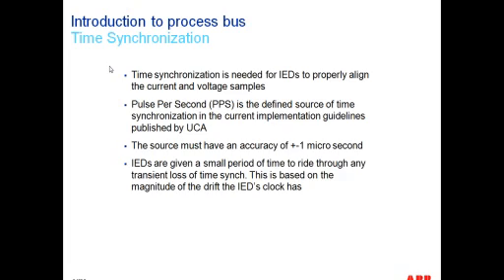Once that allowable time expires, and that time again is based on the drift of the clock, the samples published by that merging unit will have a false in the flag of that Ethernet frame associated with time synchronization. And based on the design decisions that were made, that would in turn potentially make the relays disregard those samples.